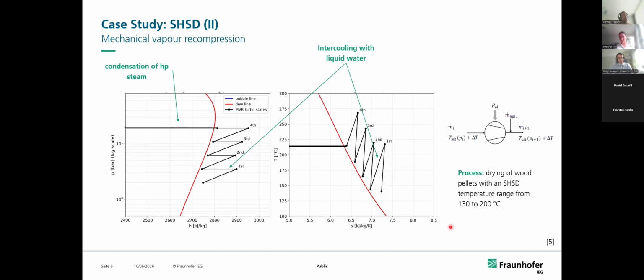This process was used to dry wood pellets. Here the superheated steam was sucked up at 130 degrees Celsius, then compressed to above 200 degrees Celsius. The condenser would be applied here, and it would be able to superheat the steam that wasn't compressed in the stages up to 200 degrees. Let's get into the more technical aspects.